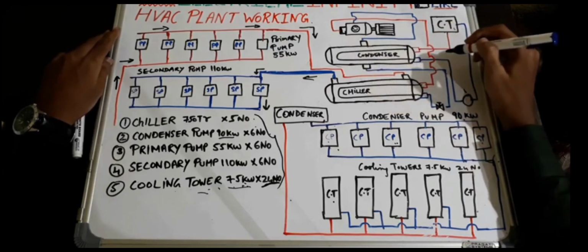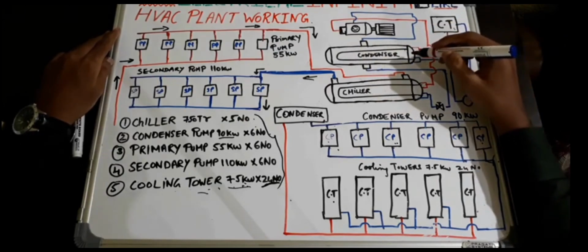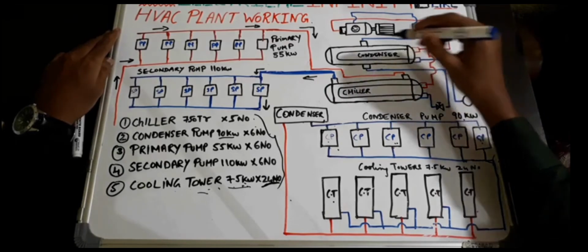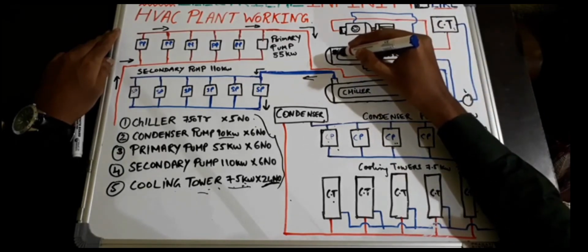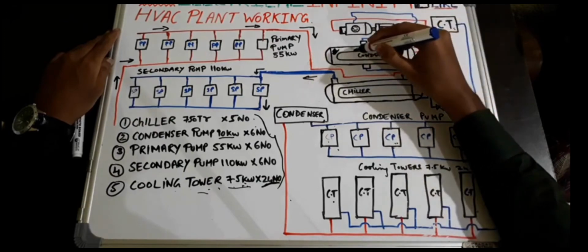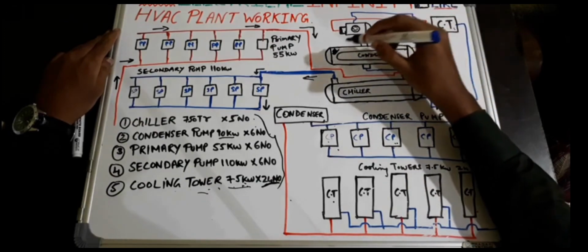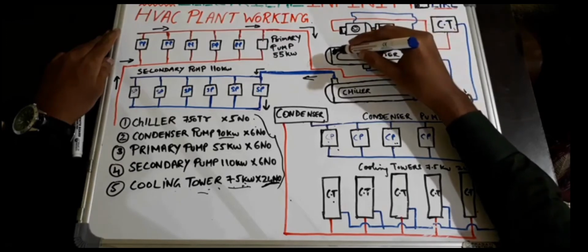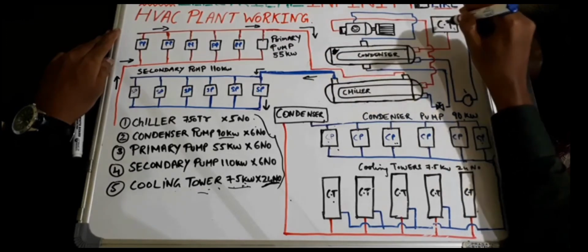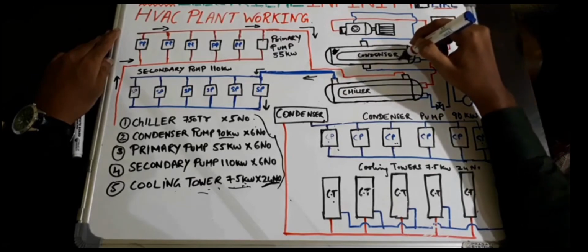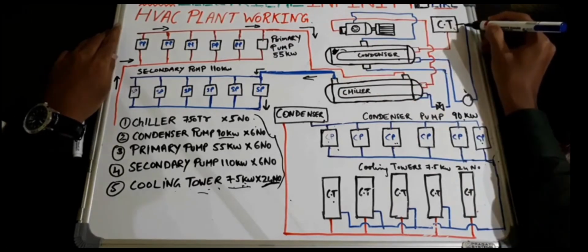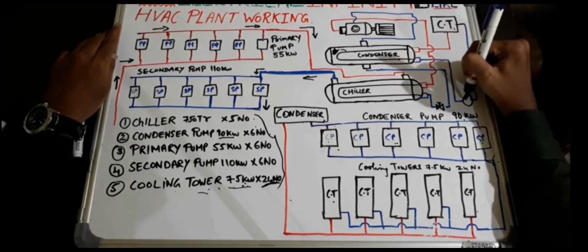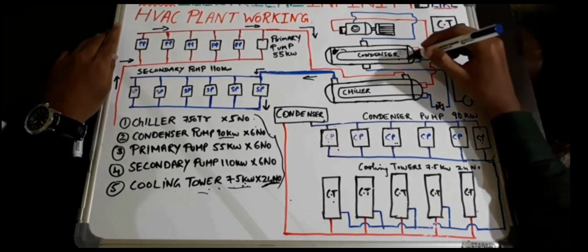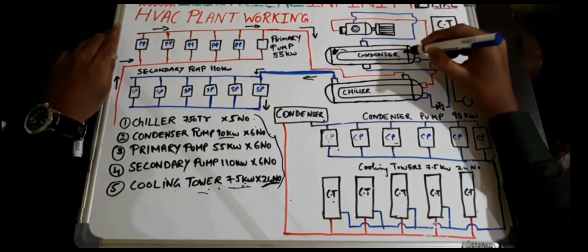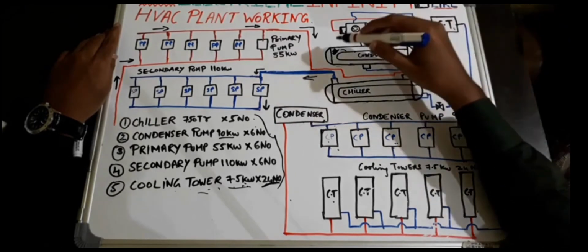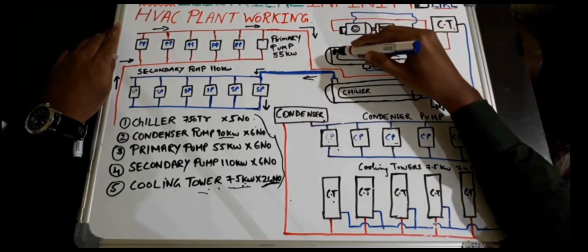So now let's begin the working of it. The refrigerant from the condenser is present in the shell type. Here you can see this section is the shell type, and this one is the tube type. So the refrigerant in the condenser is present in the shell type and the water from the cooling tower is present in the tube type. The cool water from the cooling tower is sent to this condenser pump, and from this condenser pump the cool water is pumped into the condenser, as you can see here. So the cool water is present in the tube type and the refrigerant of the condenser is present in the shell type, as you can see here.